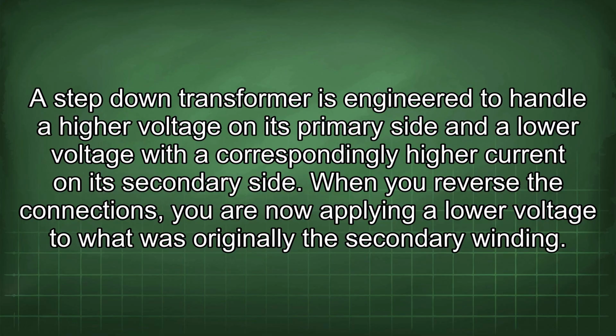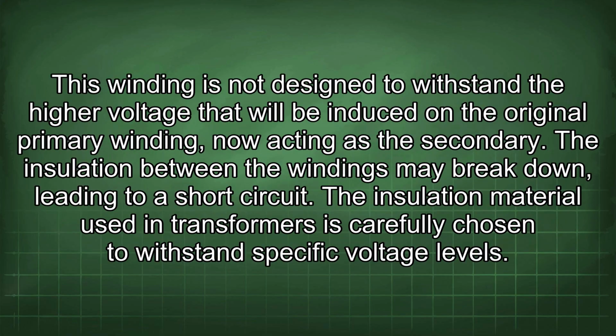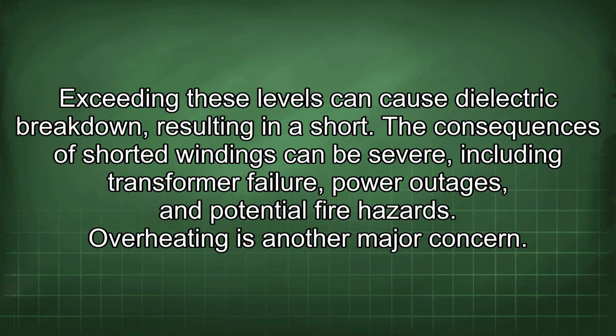When you reverse the connections, you are now applying a lower voltage to what was originally the secondary winding. This winding is not designed to withstand the higher voltage that will be induced on the original primary winding, now acting as a secondary. The insulation between the windings may break down, leading to a short circuit. The insulation material used in transformers is carefully chosen to withstand specific voltage levels. Exceeding these levels can cause dielectric breakdown, resulting in a short. The consequences of shorted windings can be severe, including transformer failure, power outages, and potential fire hazards.